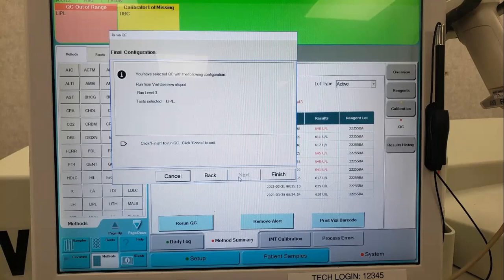If the QC still doesn't pass, we're going to look and see when it was calibrated last. If it has been a couple days, we'll just go ahead and calibrate it. And then we will run QC again after we check and make sure the QC that is on the machine hasn't been on for too long. If it's getting low, if it has less than half of what it was loaded with, I will normally pull it off. With having two Vistas, there's normally another set of QC already loaded on the machine. They are slightly off sync, and so one will normally have more than the other because we use one more than the other.